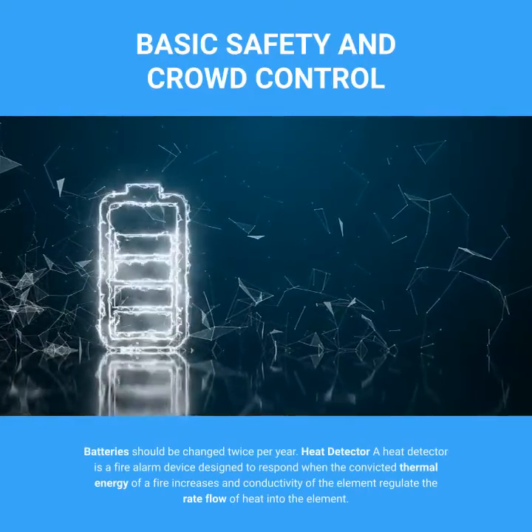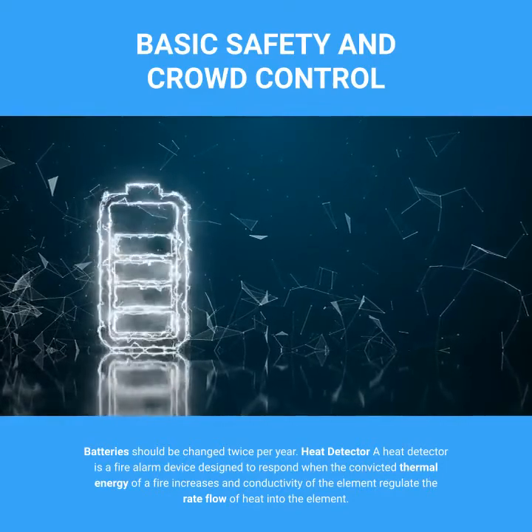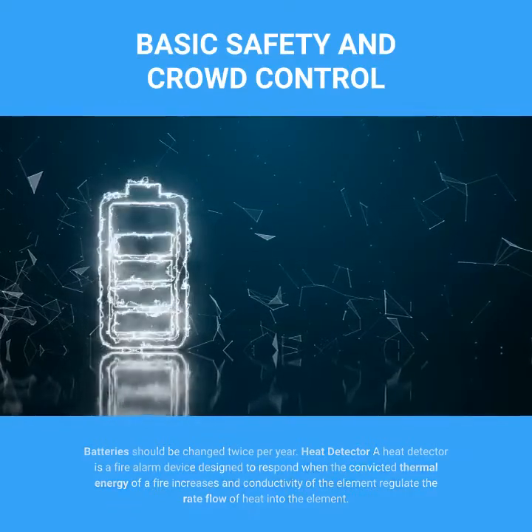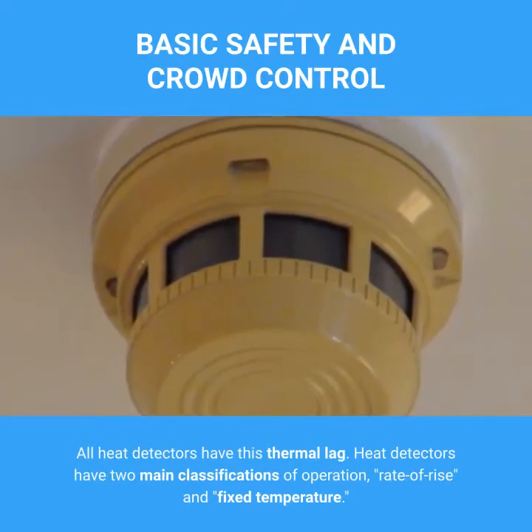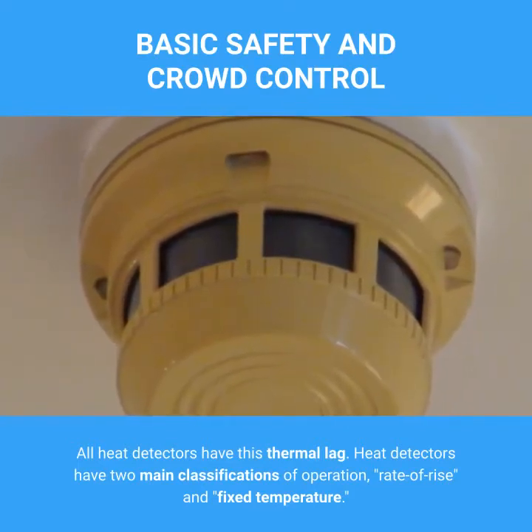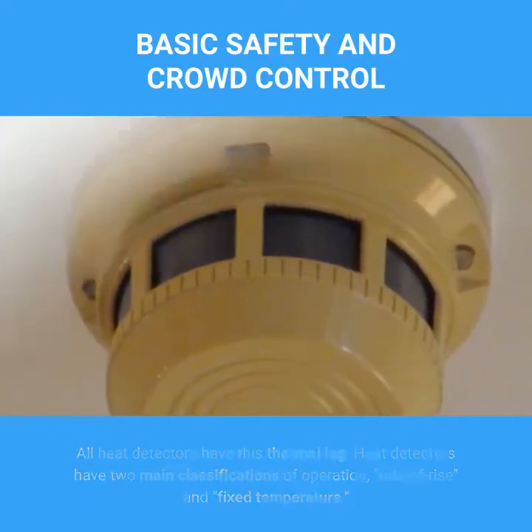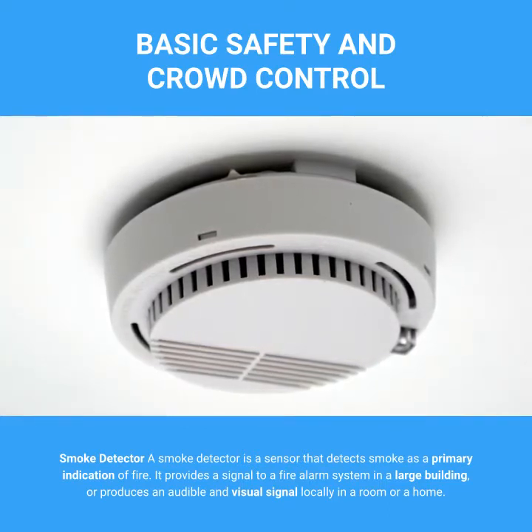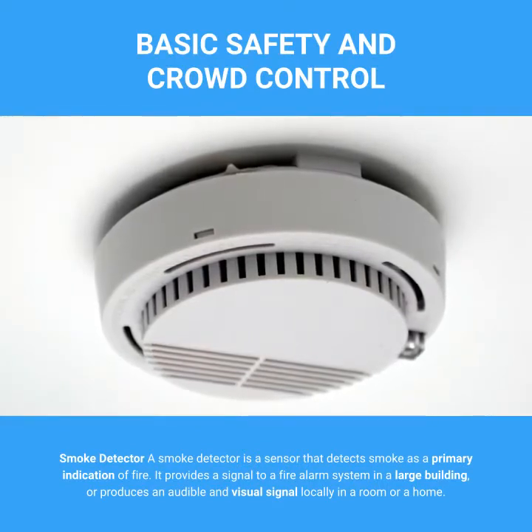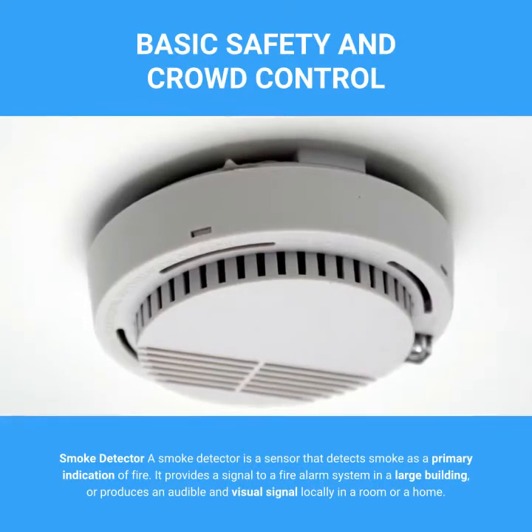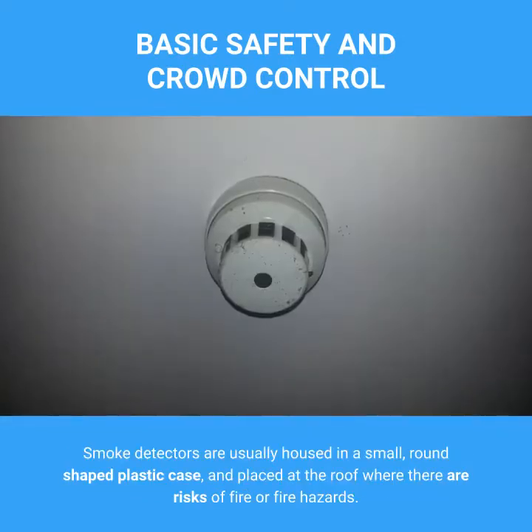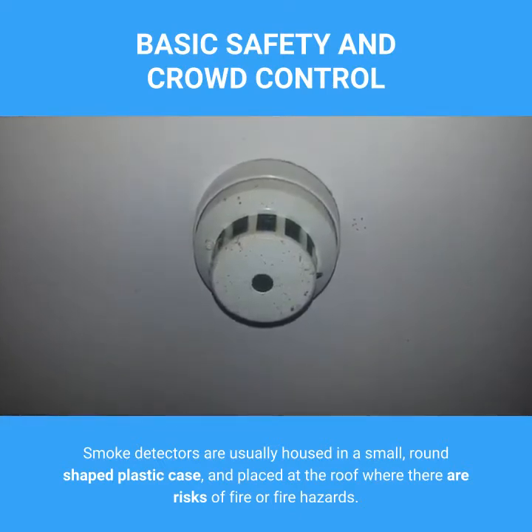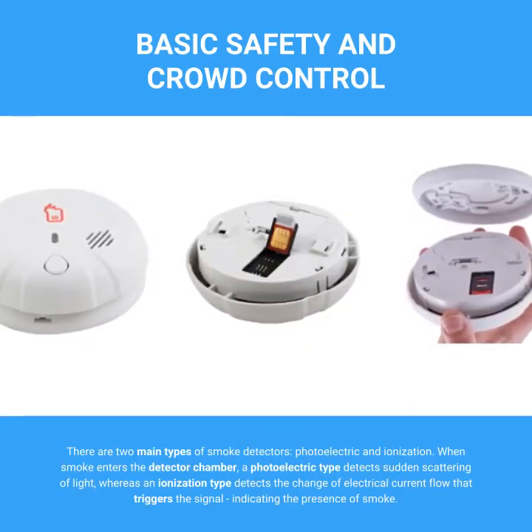Heat detector: A heat detector is a fire alarm device designed to respond when the convected thermal energy of a fire increases; conductivity of the element regulates the rate of heat flow into the element. All heat detectors have this thermal lag. Heat detectors have two main classifications of operation: rate of rise and fixed temperature. Smoke detector: A smoke detector is a sensor that detects smoke as a primary indication of fire. It provides a signal to a fire alarm system in a large building or produces an audible and visual signal locally in a room or home. Smoke detectors are usually housed in a small, round-shaped plastic case placed at the roof where there are risks of fire or fire hazards. There are two main types: photoelectric and ionization.